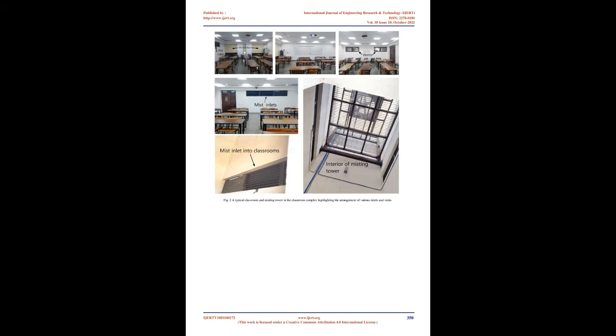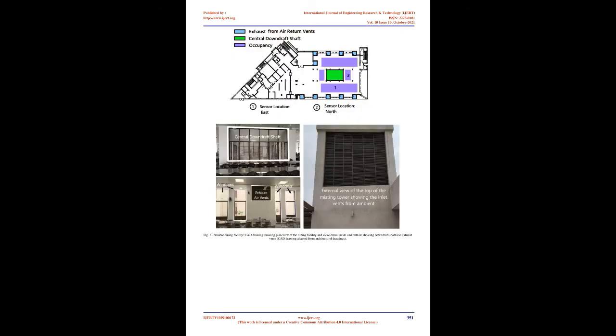Upon further observation of the issue of lower efficacy on the first floor, it was realized that balancing of the airflows between the two floors in the classroom complex was not appropriately planned, and it was difficult to amend this without serious infrastructural interventions owing to the more complex flow paths and sharper turns in the flow paths. On the other hand, in the student dining hall, not only is it easier to change the angles of the louvres, it was also realized that a set of cross baffles that were initially proposed by the design consultants were left out during the constructions.